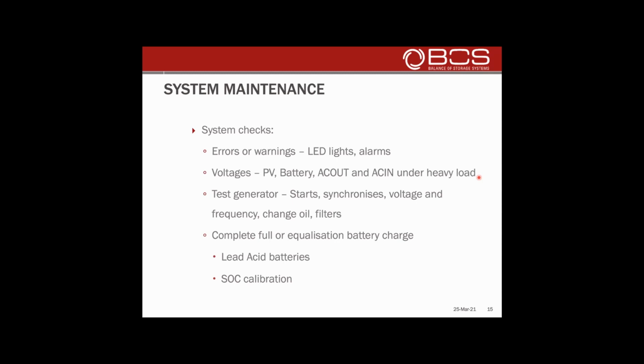And for some battery types, complete a full or equalization battery charge. That's specifically important with lead acid batteries - they need to get to a solid 100% quite regularly to ensure they're being well looked after. Doing that also helps calibrate the state of charge of the system, since whenever it gets up to 100%, it calibrates the state of charge reading, which is important.